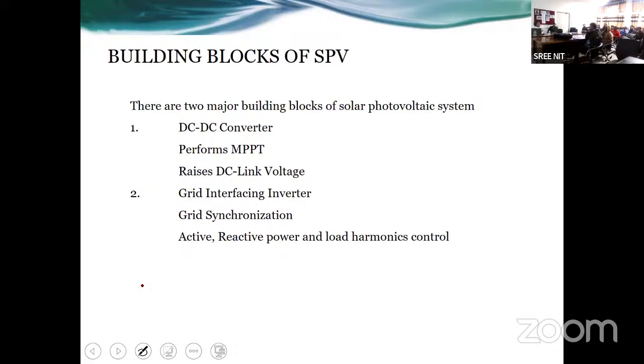Now, in the earlier scenario, the renewable energy sources had to get disconnected from the main grid in order to protect themselves under fault conditions on the grid, and they got connected again when the system improved. But now this tendency is not there, because a fault means you need to feed reactive power. So now those converters are required to stay connected, and they must prevent the flow of active power while utilizing the capacity for supplying reactive power and harmonics. We call it low voltage ride through capability, LVRT capability.